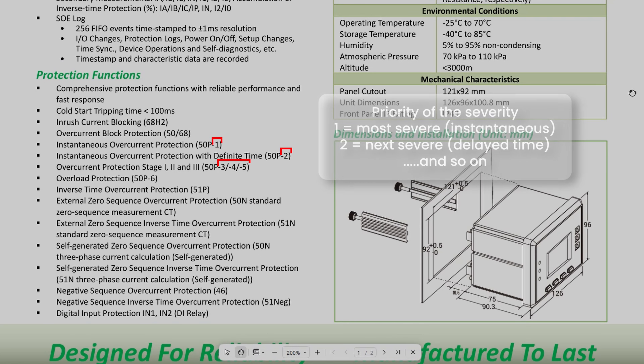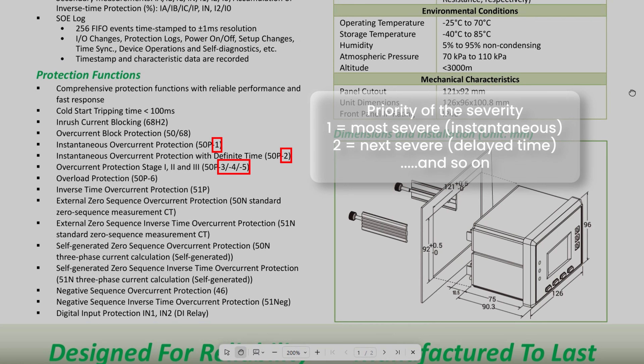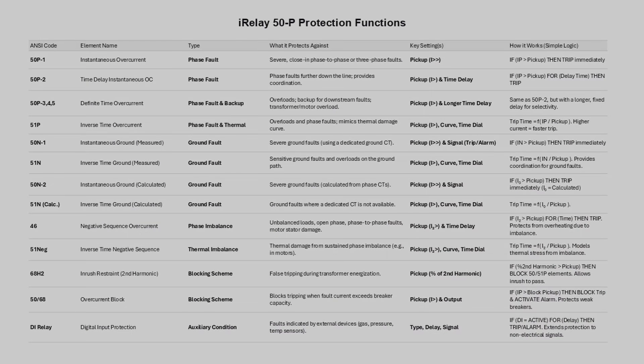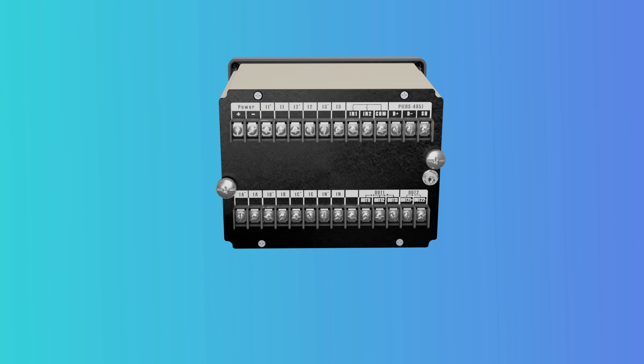The N protection is for the ground fault. Next, the stage numbers: stage one is instantaneous protection for severe faults, stage two is time-delayed protection for less severe faults, and so on. I have summarized them into a table for easier comparison.